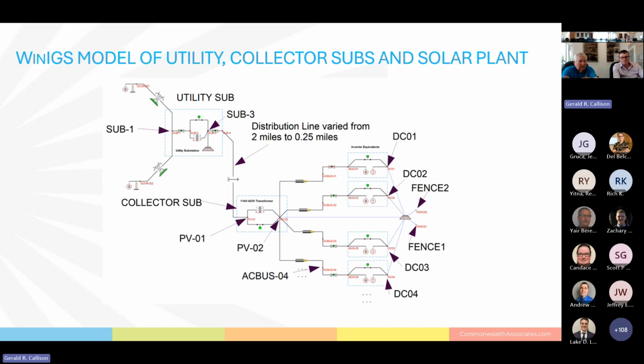So this is the WinIGS model that we're going to use to show the interaction between the different facilities. You have two lines coming into a utility substation, and that substation has the 115 to 11 kV delta Y transformer. We're going to vary the distance of the distribution line from 2 miles to a quarter mile, which basically puts the two substations from 2 miles to a quarter mile apart. And then we have the collector station that has the 11 kV to 425 transformer in it.